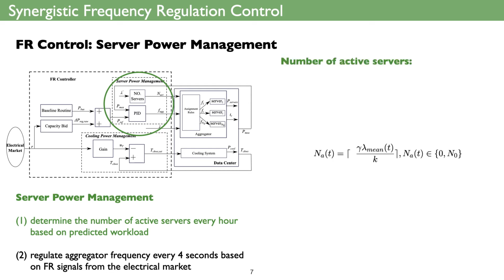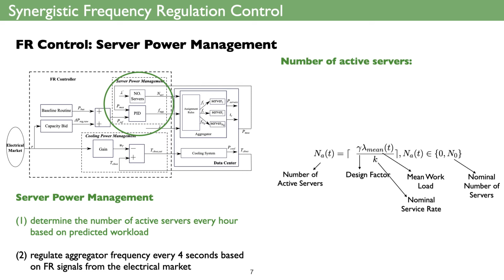So for the first one, the number of active servers, we choose to modulate the number of active servers every hour because the servers actually take a relatively long time to be activated or deactivated. This equation shows the number of active servers at each hour based on the predicted workload and the service rate that a server actually can operate at. The division of these two gives us the number of active servers.